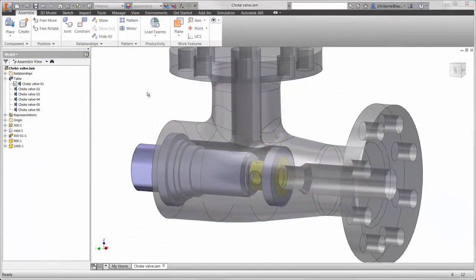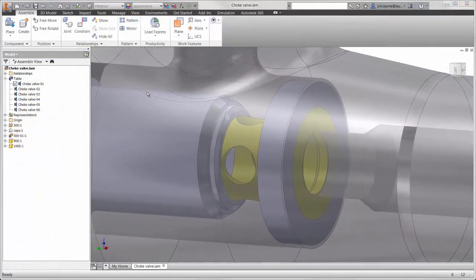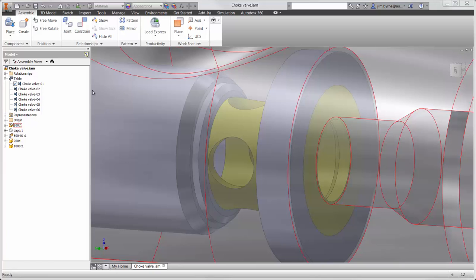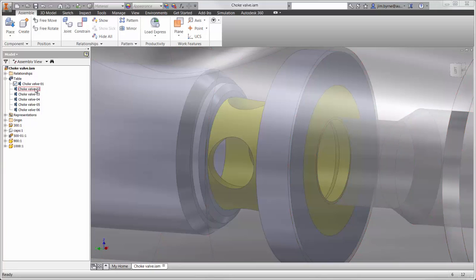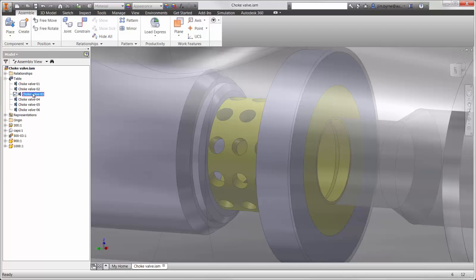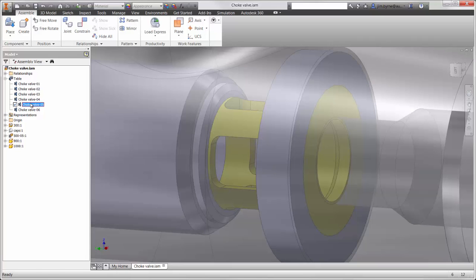On the inside of the valve, you'll notice a cage that has been inserted for a few reasons. This will make the flow more symmetric, it increases frequency levels, and directs bubbles due to cavitation away from the walls of the valve body. In the end, it will extend the life of the product and reduce maintenance costs.